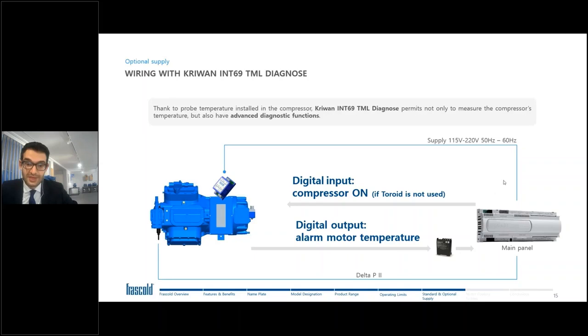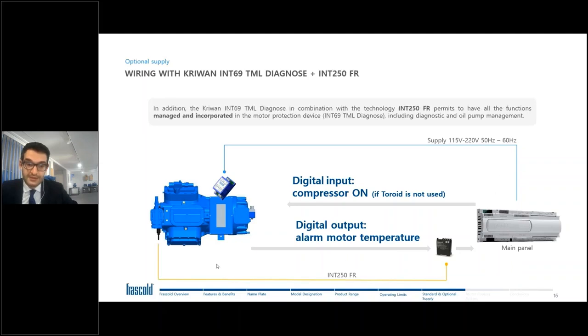Another possibility is to use another pressure switch instead of the Delta P II, the INT250 FR, that is connected directly to this device, the INT69 TML Diagnose. It allows you not to go to the main panel, but is controlled directly from it. Apart from this, the injection card and the toroid are exactly the same for all three systems.